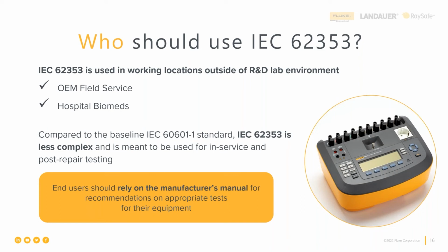So we'll talk a little bit more about this in a minute, but even in the United States, where most of us are saying NFPA 99, the IEC 62353 is just as quick. In fact, it only requires a little bit more measurements and collects the measurements for you than the NFPA 99 requires. We'll talk about that in just a minute.